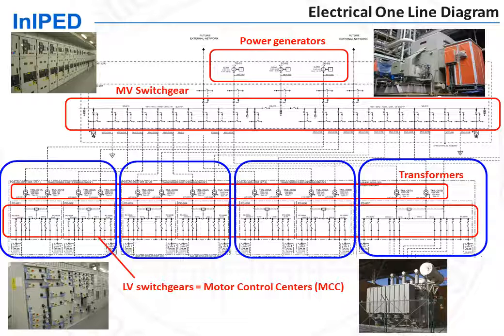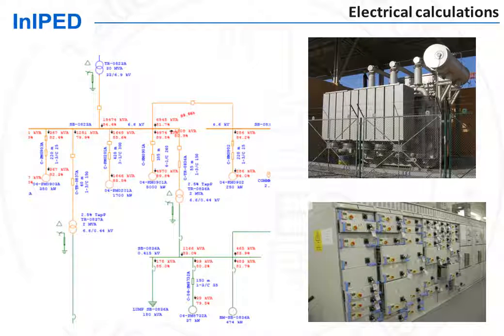Once this electrical system has been set, it is subject to calculations. The load flow analysis performs the calculation of the voltage and current in every part of the system, as well as short-circuit calculations. It allows to identify the maximum current that each equipment must be able to sustain, hence to define the rating of this equipment. Once this is done, equipment data sheets for all the equipment can be issued.